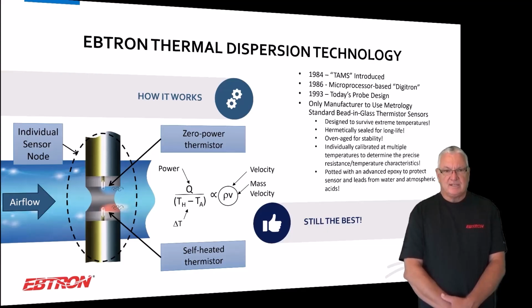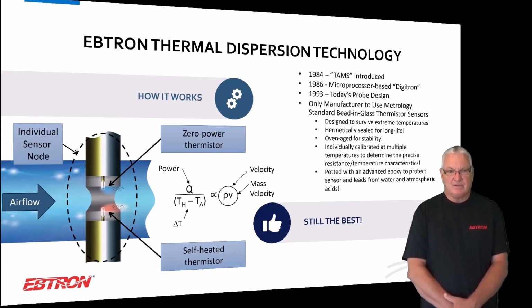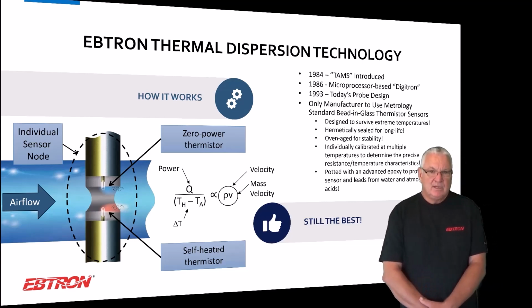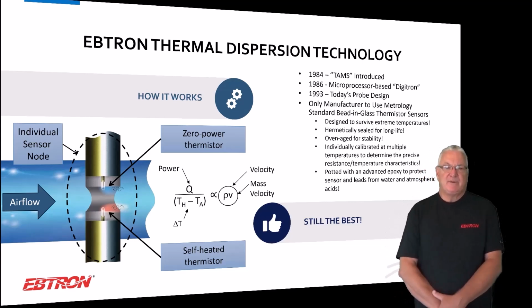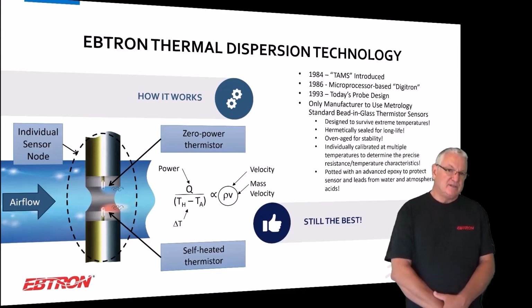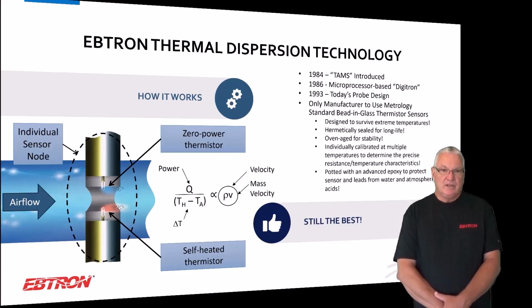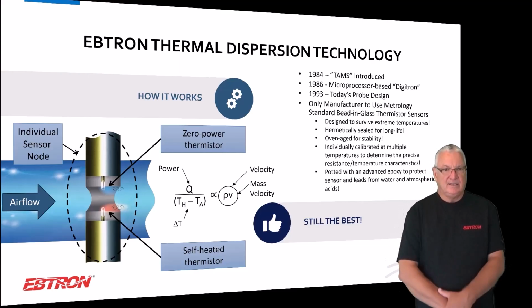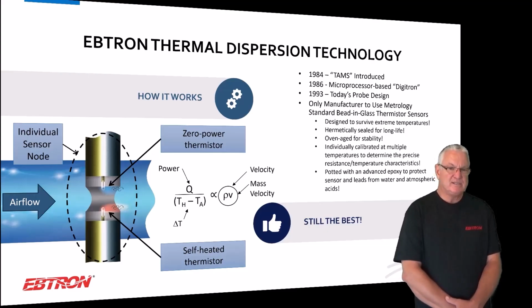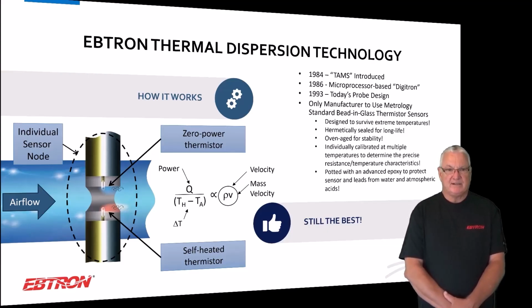But each one of these sensor nodes has two thermistors. And one thermistor is self-heated, which means we pass a little bit of current through it, we heat it up, and as a result we can measure the power dissipated to the airstream, and because it's a thermistor we can basically determine what its body temperature is. We have another one we call a zero power thermistor, which is microamps of current, no self-heat, it measures the ambient air temperature.